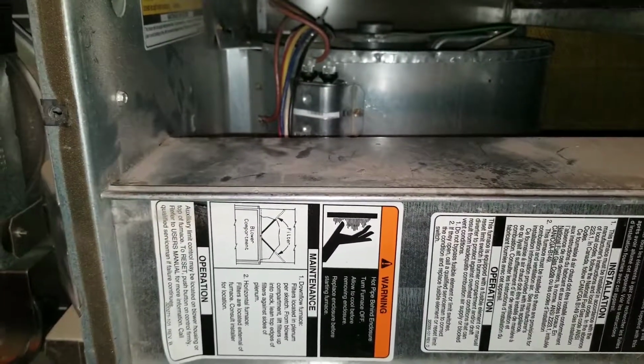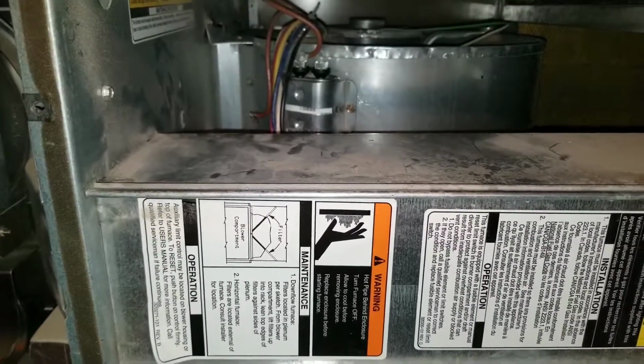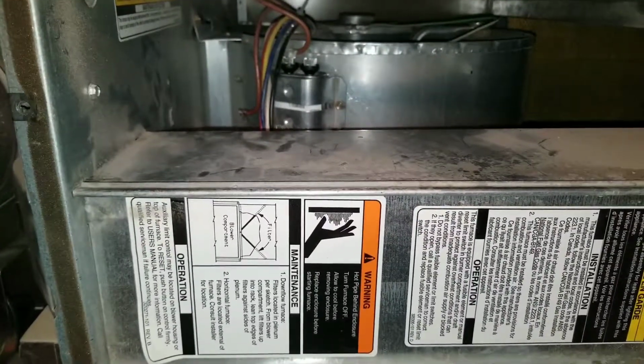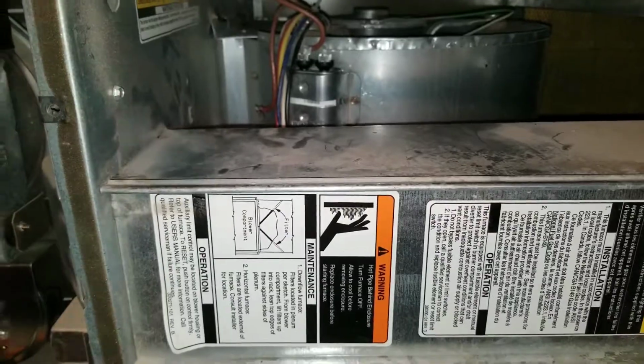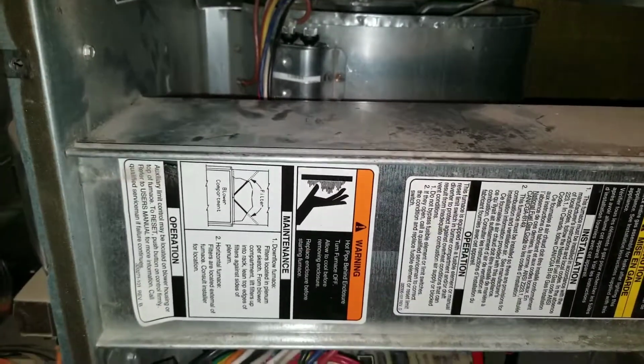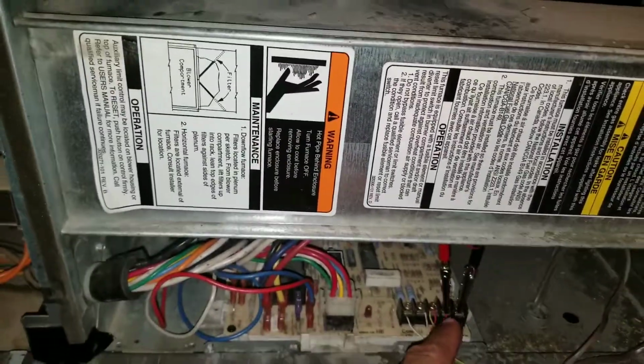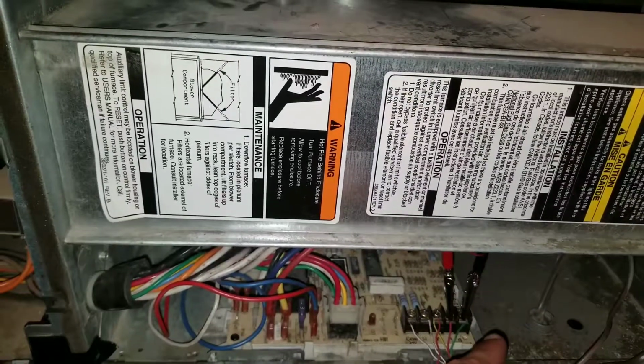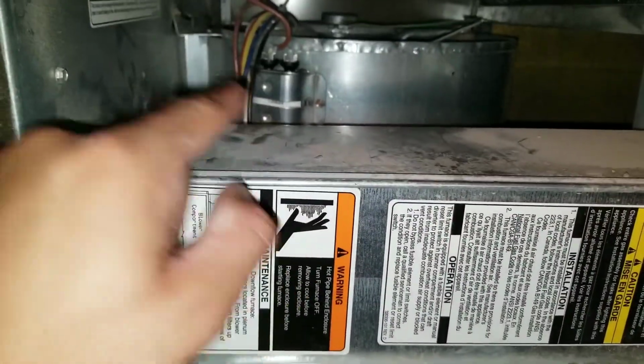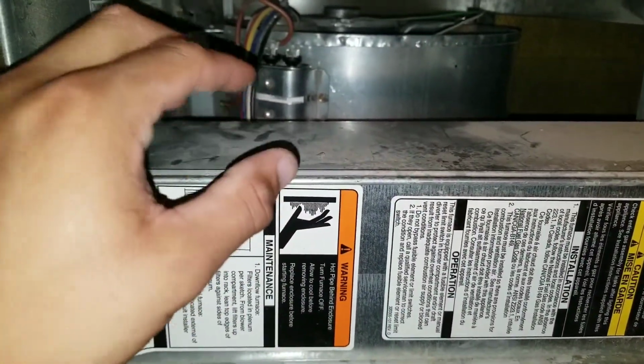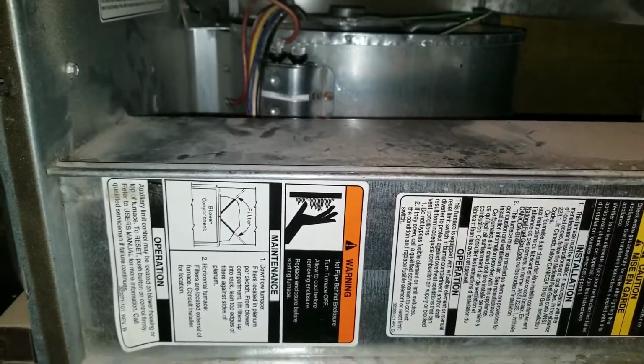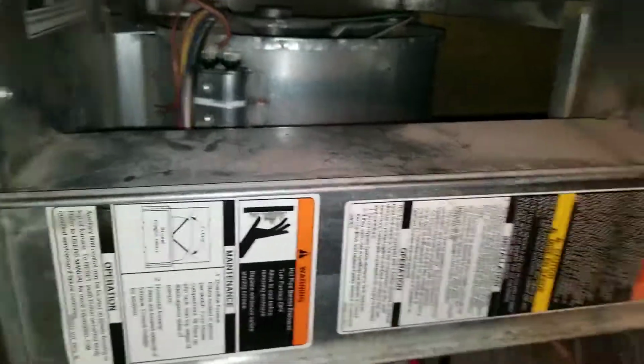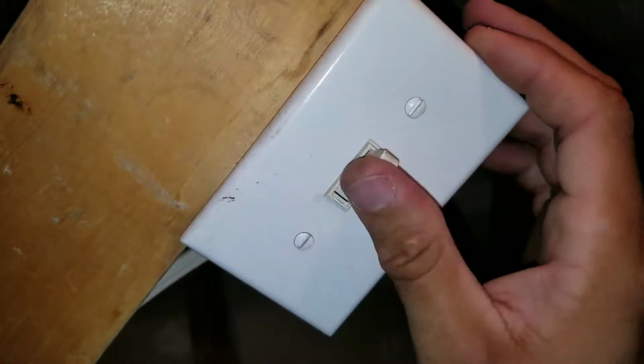If I listened and I did not hear my blower motor turning on, I would know that there's an issue. So instead of going up and down, back and forth, here I'm at the blower motor. I've jumpered out my R terminal and my green terminal. Right now I removed my wire from my capacitor, so this would act as if I had a bad capacitor.